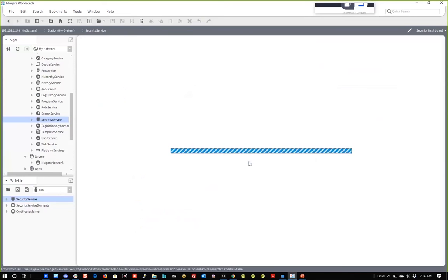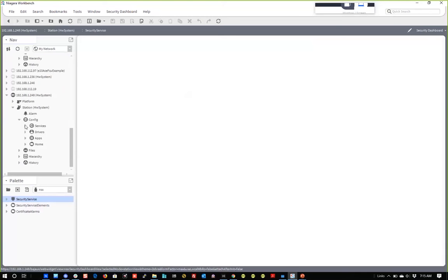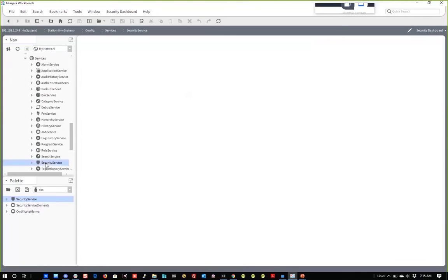Hopefully this comes up. I got this feature for the supervisor enabled last night. So it's the first time I've gone to see if I can get it to go through from the supervisor out to the edge device, which doesn't look like it's getting there for some reason. There may be a feature I need to put out there because when I dropped it on that Edge 10 the other day, I had the same thing. So it's something that's not set up properly in my Edge device because when I go in there, I get the same blank screen. So we'll just go back and look at the supervisor station.